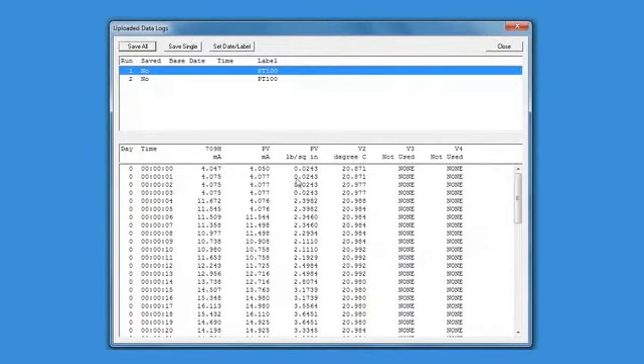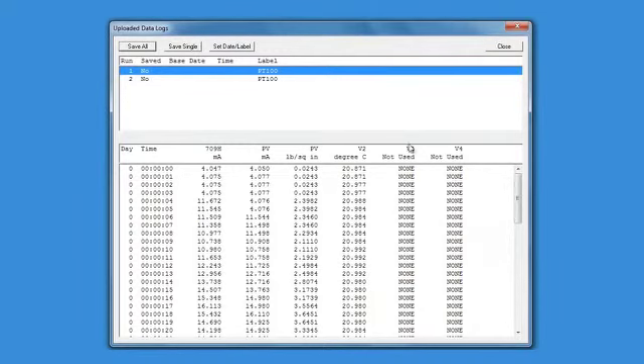Each data sample contains the 709H milliamp measurement, the milliamp PVAO, and all four HART process variables. The upper window displays the logged events by device ID, and the lower screen shows the individual measurements of the logging session.